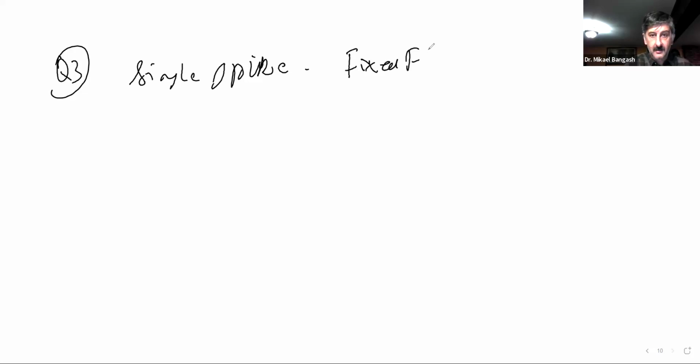And we have a pulsed array, phased array, we have a continuous wave, and we have a pulsed wave, single crystal. The word here is the single spike, because that single spike is going to lead to a fixed focal point, or one single PZT.